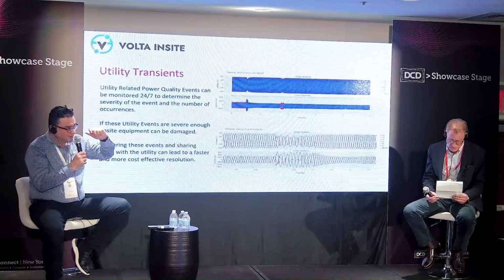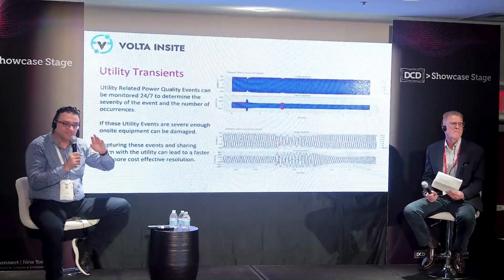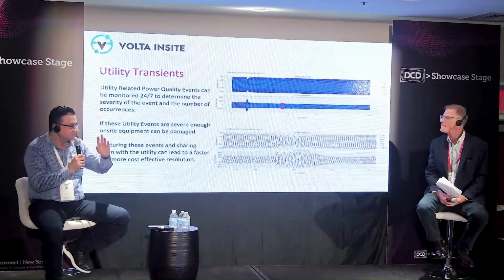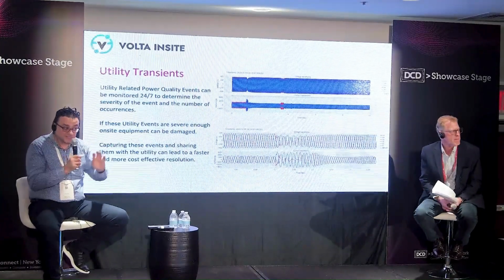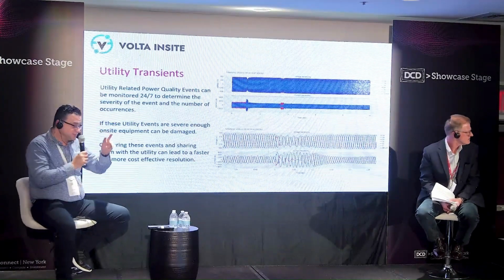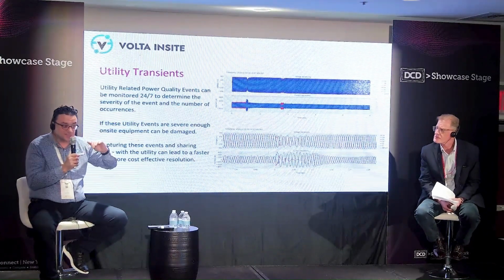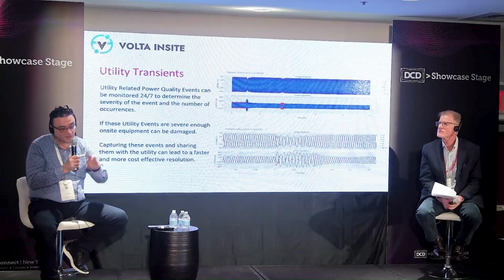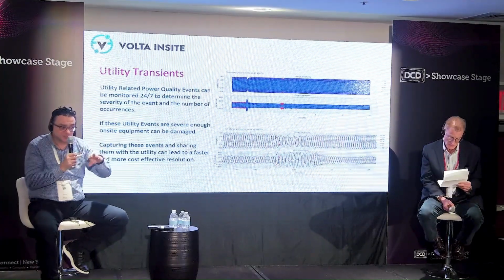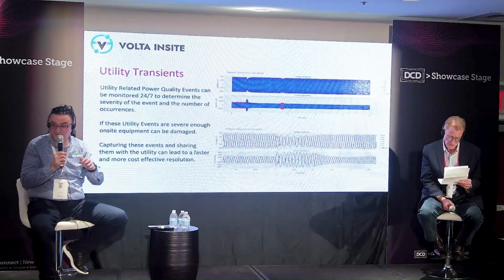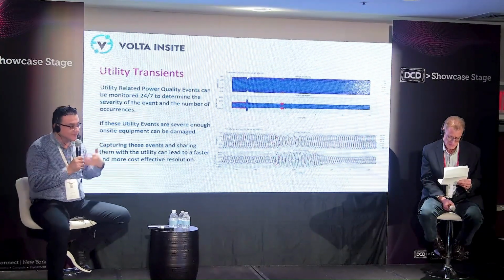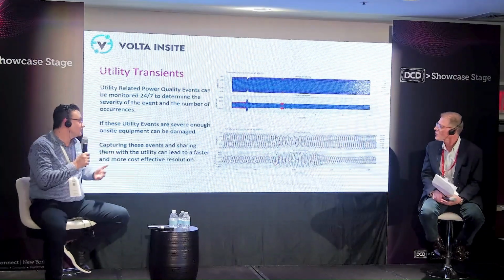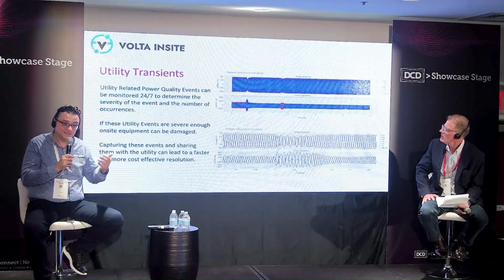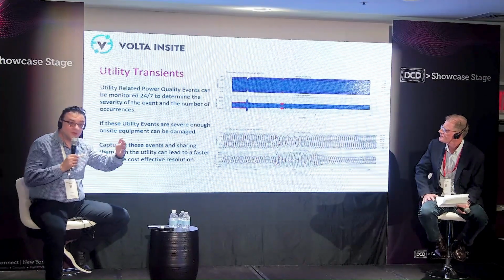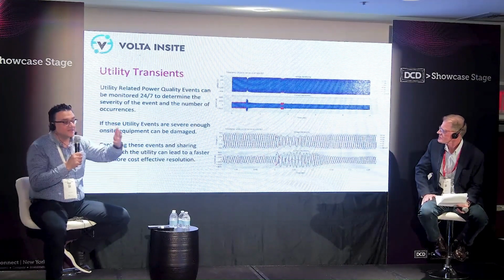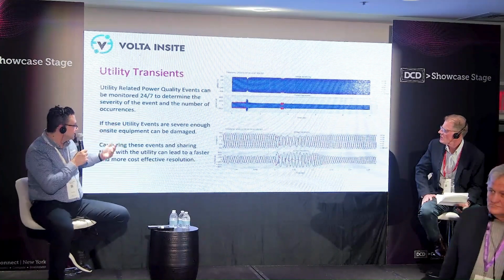We're also able to create specific thresholds and event captures for our system. There are two things that enable us to run this continuous capture: one is the hardware we've built and the algorithms for compressing that data and maintaining it in the back end so we don't blow up with too much data. The other piece is that we're running this continuous waveform capture, which gives us flexibility into electrical signature analysis.